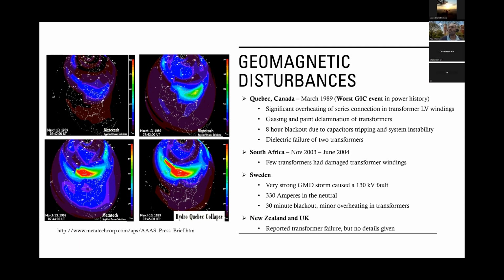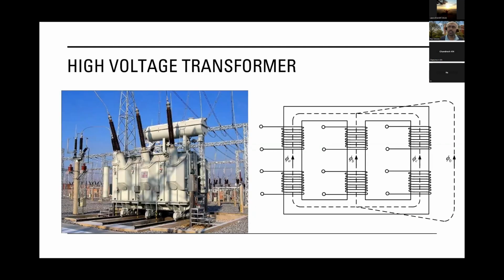People often ask if transformers blow up. They're pretty hardy devices, so they overheat and then they trip off the line. There are protection devices that, if there's a fault in the transformer, take it out of service before there's any serious catastrophic explosion. There have been explosions, but as far as I know, not due to GICs. The temperature rise usually trips off the transformer before a severe explosion occurs. So here's a typical high voltage transformer. Just so you're aware, these transformers can have voltage ratings from 230 kilovolts to 345, 500, and 765 kilovolts, which are the more common transmission level voltages that we use.